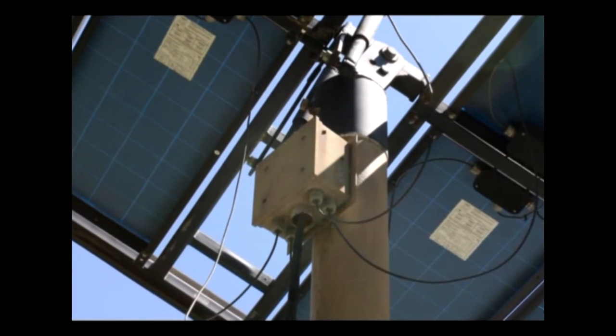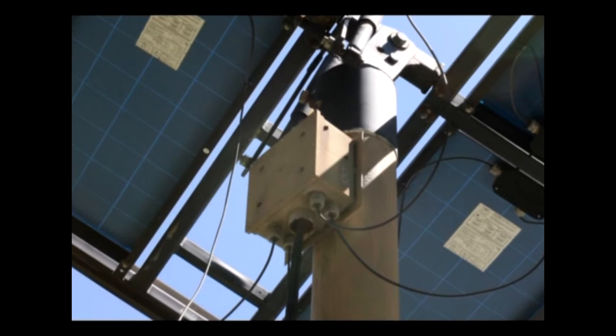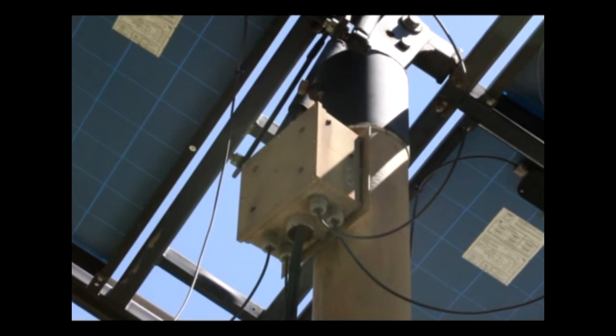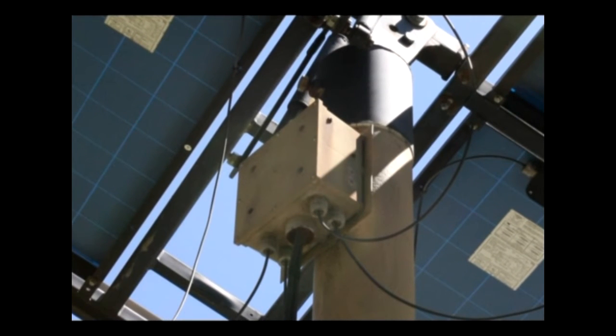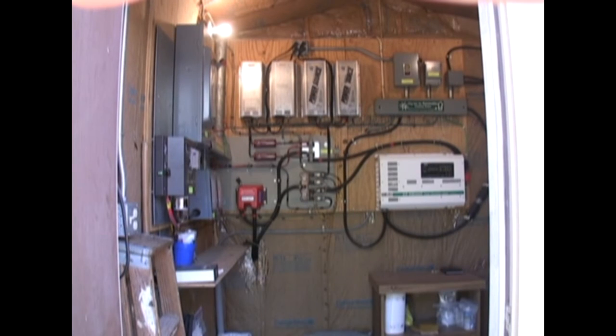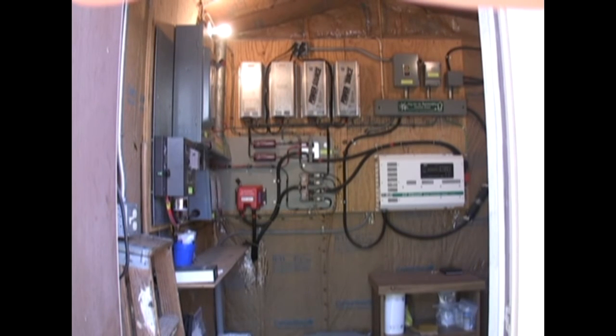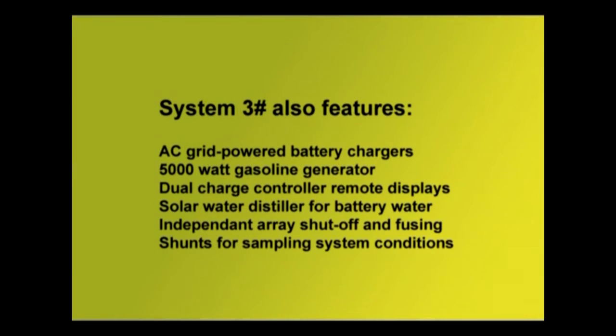As you can see, a combiner box was used to take the outputs of each set of 3 and parallel connect them to add up the amp hours inside of the combiner box. Then, just plus and minus comes out with the black cable. This installation utilizes a small separate building for the equipment and the batteries, and it has it cut into 2 rooms. This equipment room looks more complex because this system has a bunch of extra features built in, like AC grid-powered battery chargers, so you can charge the entire battery bank from the commercial mains if you wanted to. It has a 5,000 watt gasoline generator as a backup.